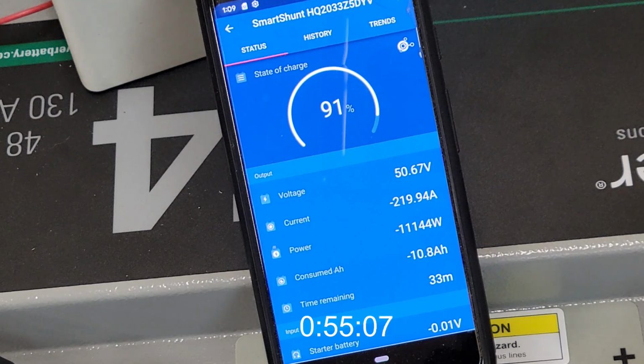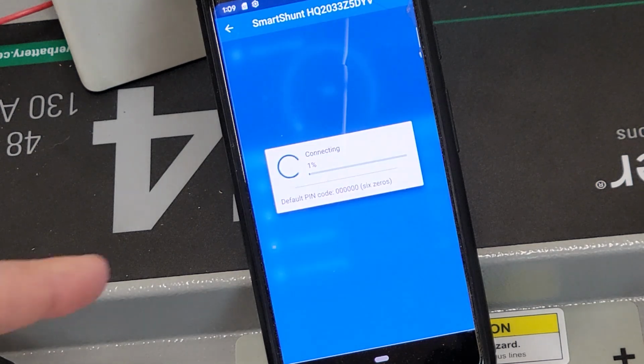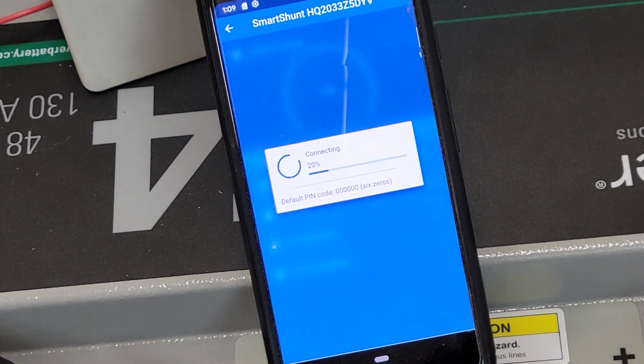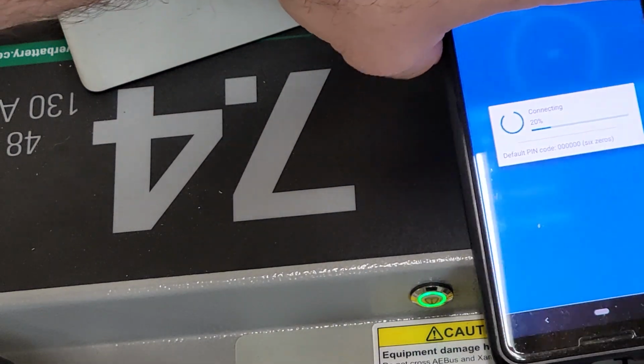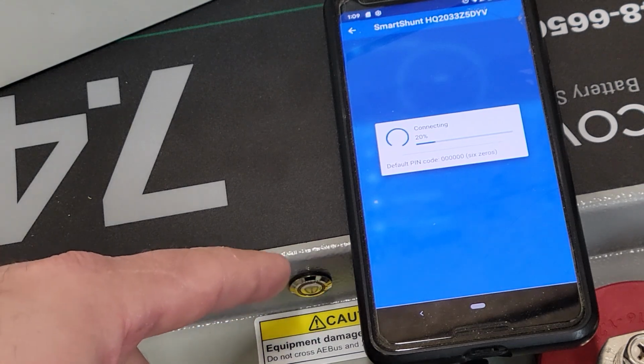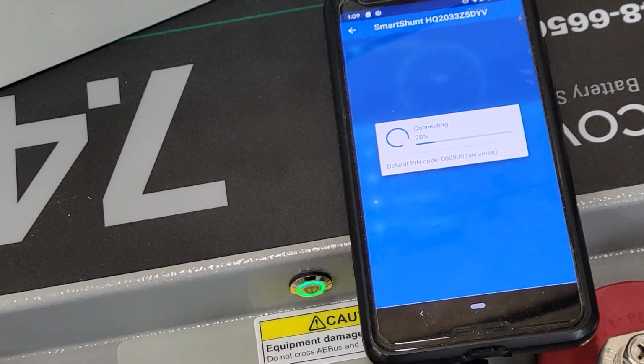Wow, it's definitely been over a minute. I mean, I'm shocked it's doing it. All right, and there we go, it just shut itself off. And we lost signal because the BMS shut off. If I move this over, yeah, see the flashing LED? I want to see if the BMS will automatically turn itself back on. That was a really long duration. I'm actually really shocked that it handled it. That was over 10 kilowatts being pulled from the inverter on the AC side.